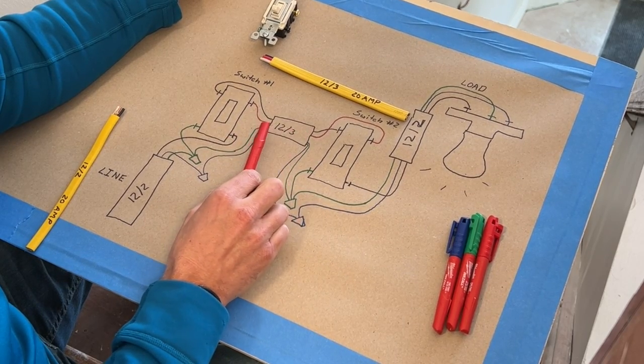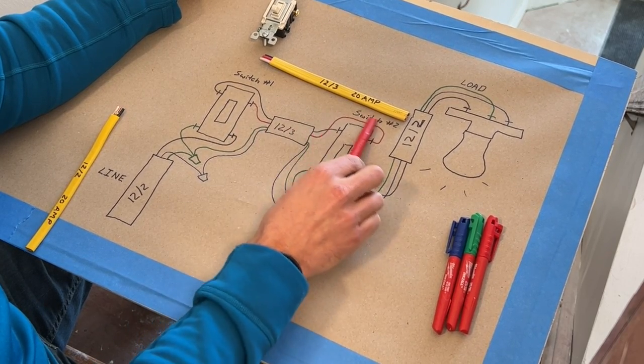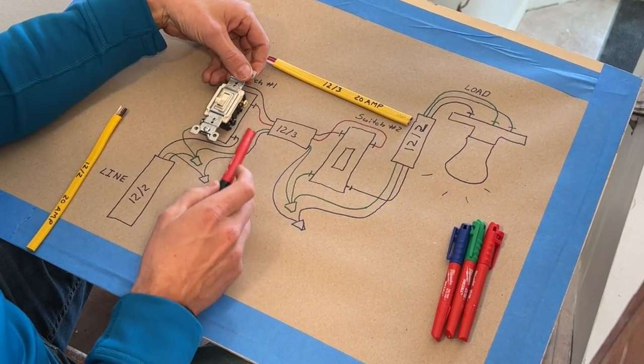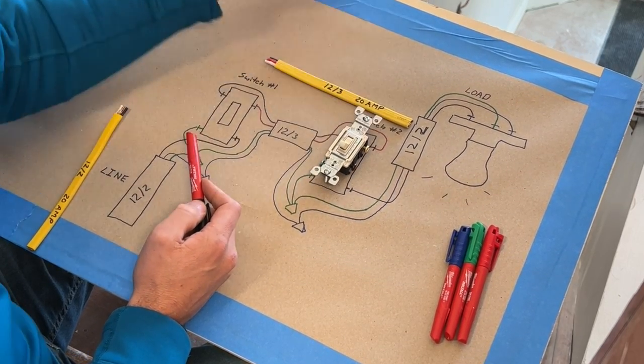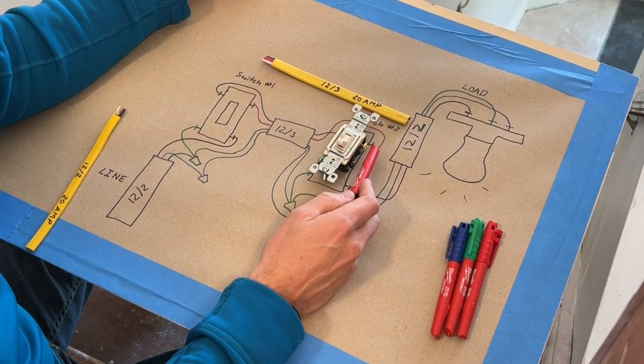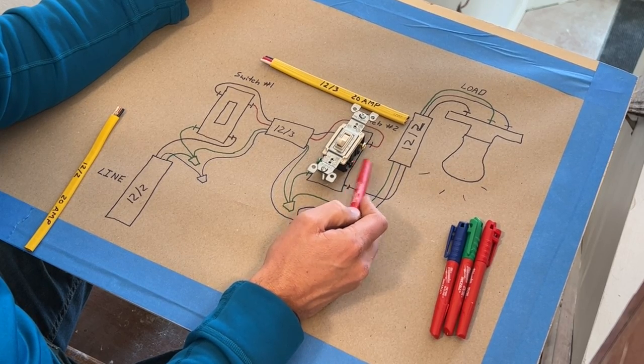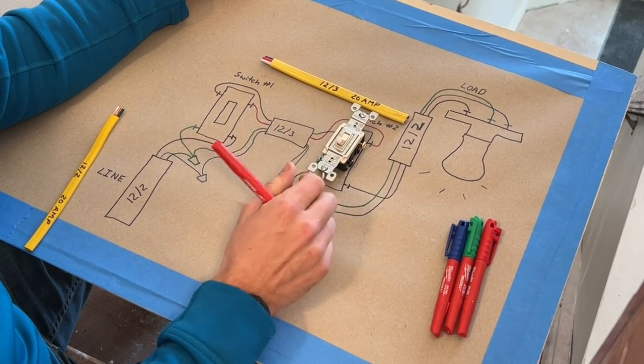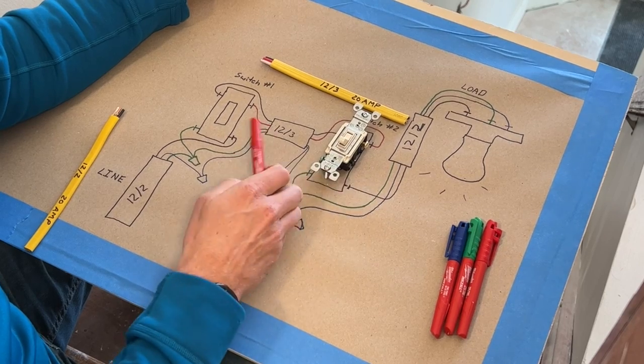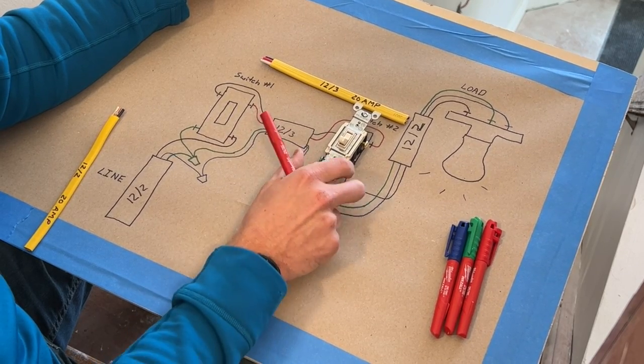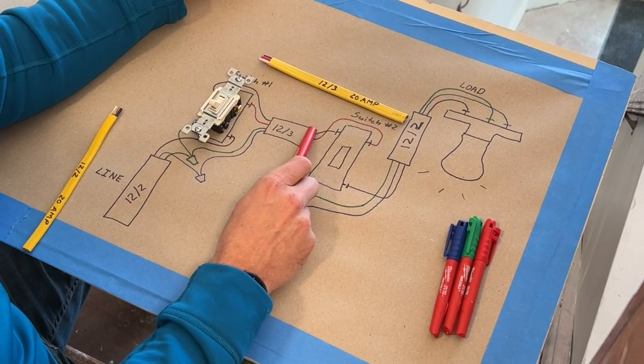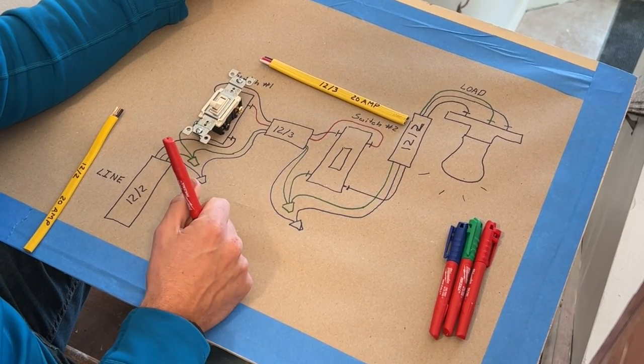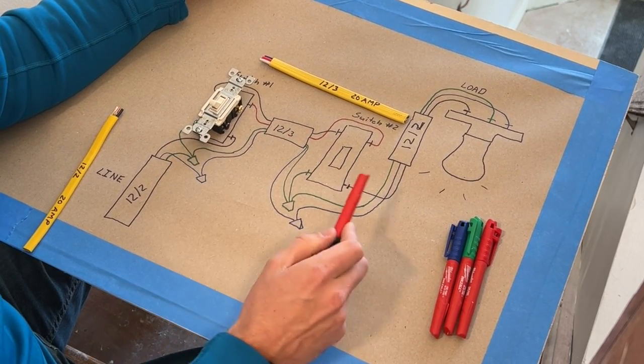Then in the same fashion, the travelers are connecting up. So in this case, I would have red coming in here. And then on the other one, I would also pass red into the same side as the black common. Now that is not critical - it should work if you took red to this side, but I just like to be consistent. And as such, I took the black to my top traveler terminal.